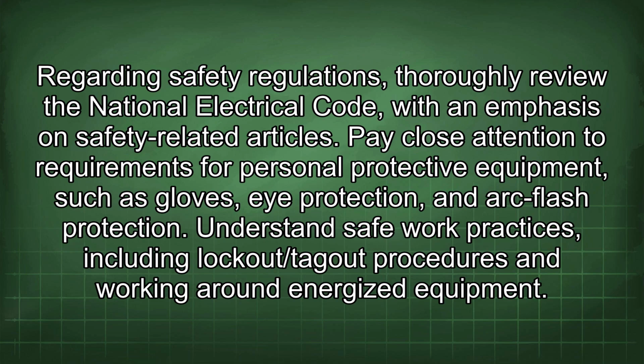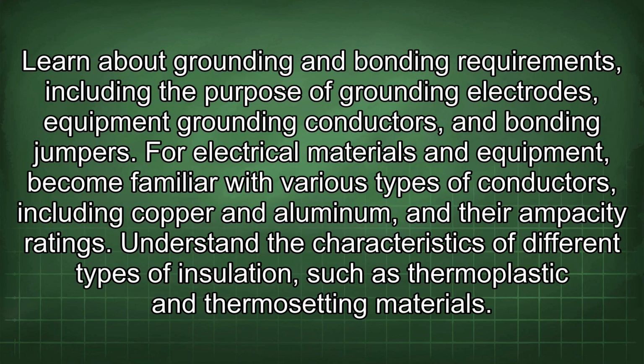Regarding safety regulations, thoroughly review the National Electrical Code, with an emphasis on safety-related articles. Pay close attention to requirements for personal protective equipment such as gloves, eye protection, and arc flash protection. Understand safe work practices, including lockout/tagout procedures and working around energized equipment. Learn about grounding and bonding requirements, including the purpose of grounding electrodes, equipment grounding conductors, and bonding jumpers.